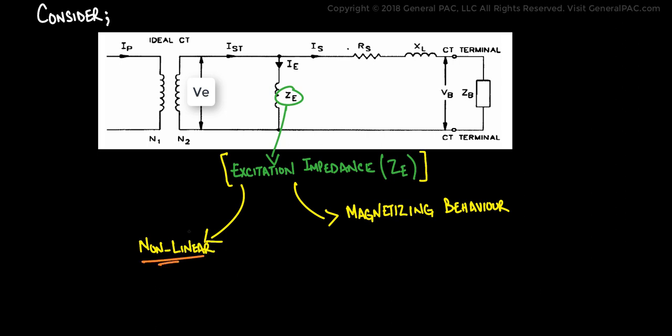Which means that this impedance changes as the CT saturates and it results in a varying secondary excitation voltage VE as well as the varying excitation branch current IE. So, ZE is equal to VE over IE and ZE is a non-linear value. And we will go over this in much more detail later in this tutorial.